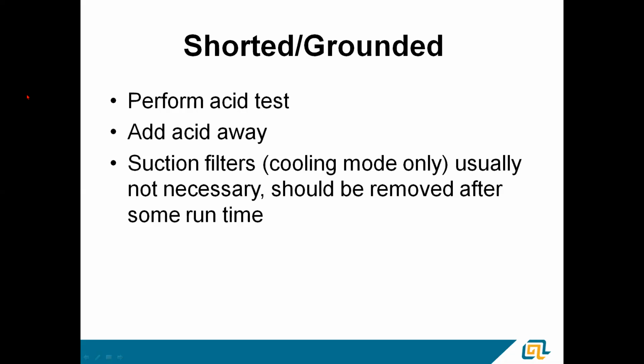Suction filters, I'm not a big believer in suction filters. You have to make sure it's in the cooling mode. If you got a heat pump, you got to make it so it cannot go into the heating mode, because that will really wreak havoc on the system. You can only run a suction filter while you're in the cooling mode. They're usually not necessary, and they should really be removed after some runtime.